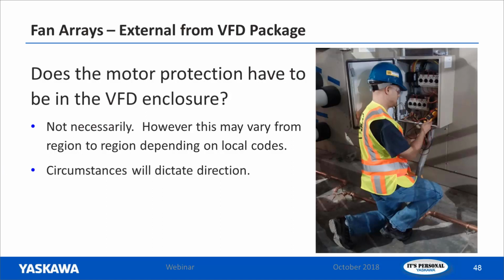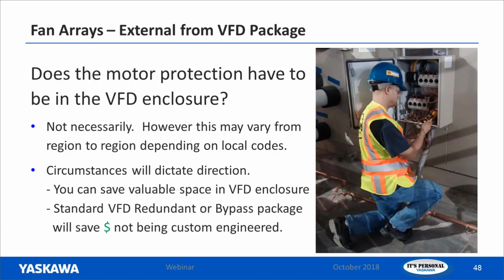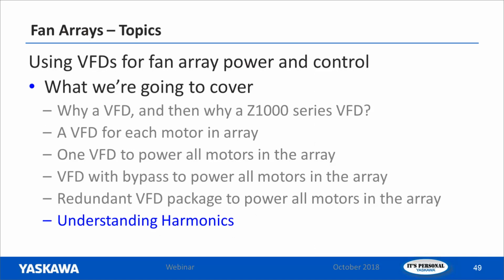Circumstances will dictate, of course, direction, but you can save valuable space in the VFD enclosure if you are doing the motor protection panel separate. And of course, you could also save money without having to have it custom engineered in the VFD panel for however many motors you need and what their horsepowers are. That pretty much covers the array detail so far of this presentation. So I'd like to shift over to understanding harmonics.